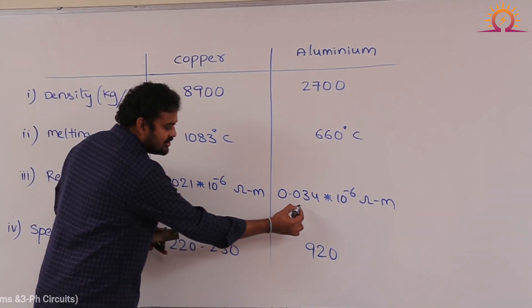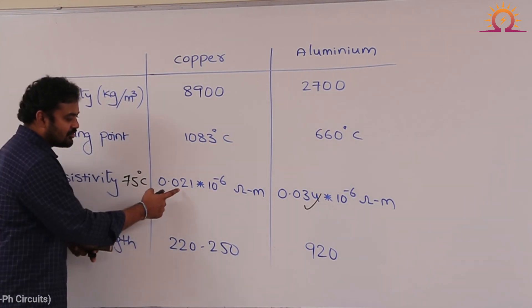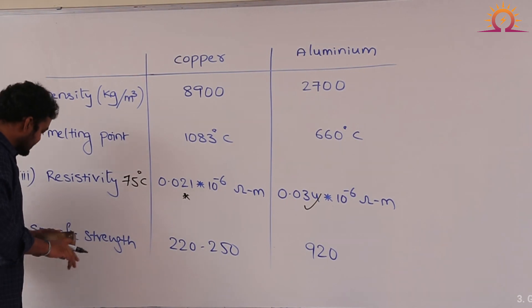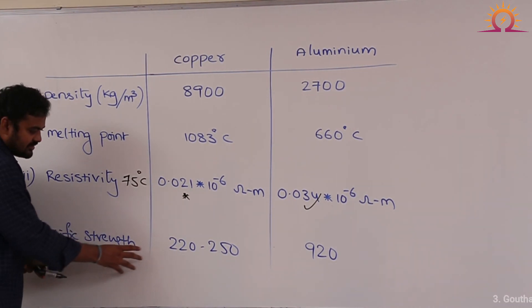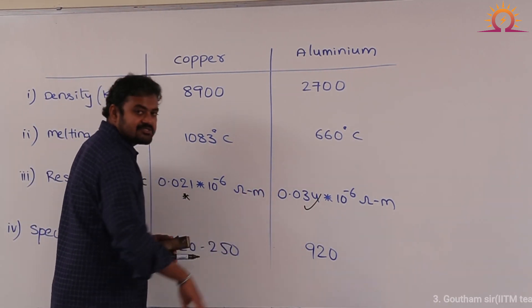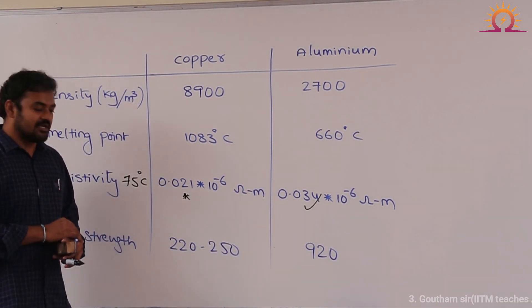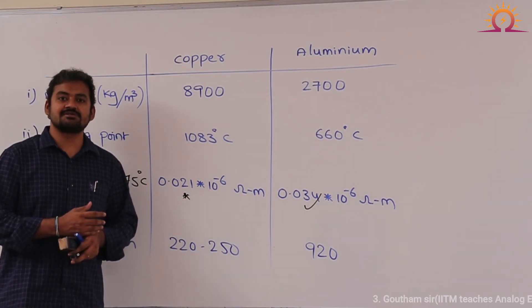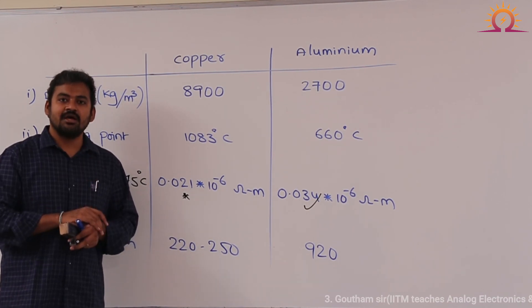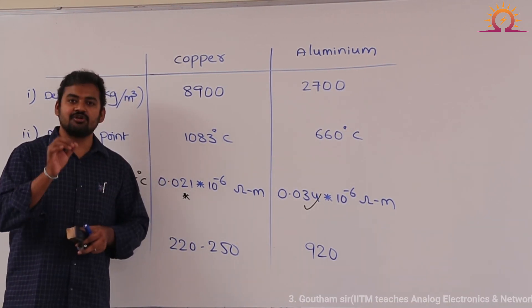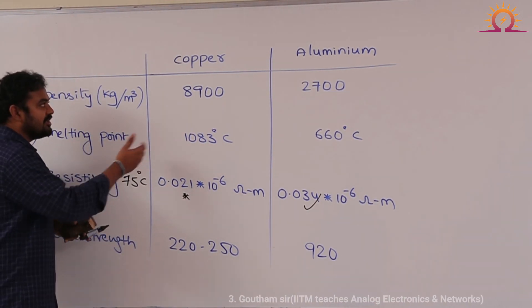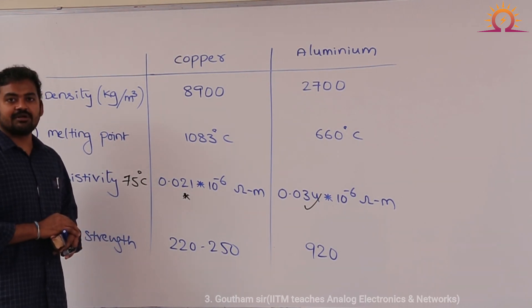Aluminum resistivity is definitely more than copper — this is one more superior quality for copper material. Coming to specific strength, it is 220 to 250 for copper and 920 for aluminum. But in electrical machines, specific strength does not matter, because the winding is inside the machine, bounded in slots and around the core. When you come to transmission lines, specific strength becomes an important aspect.